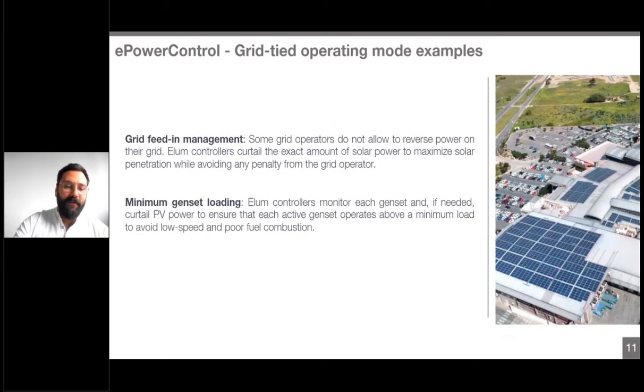So concerning the features that we will be providing for such an application, we will be providing the grid feed-in management, either the zero export or the net metering, depending on the operator and the client for sure. Once the grid is available, we will be able to do this grid feed-in management. And once there is a blackout and there is a switch to the backup gensets, we will be providing the minimum genset loading, which is the minimum percentage below which the genset preferably should not run. Otherwise you will have some additional fuel consumption and some maintenance problems. So with our controller, we will be able to make sure to provide this minimum genset loading.